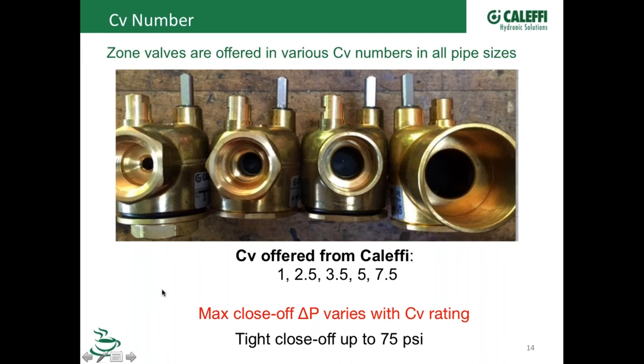While our zone valves are, I think, rated for 300 PSI static or working pressure, it's the differential pressure across that valve, from inlet to outlet, that we're really worried about. If you do happen to exceed that maximum differential pressure, which, like you said, is quite difficult to do in a residential application but in commercial applications is definitely possible, then that force is going to start forcing that paddle open, and you're going to get overheating zones. It's just going to lead to all kinds of trouble. So make sure that you're choosing the right ones, and call us if you need help with that.